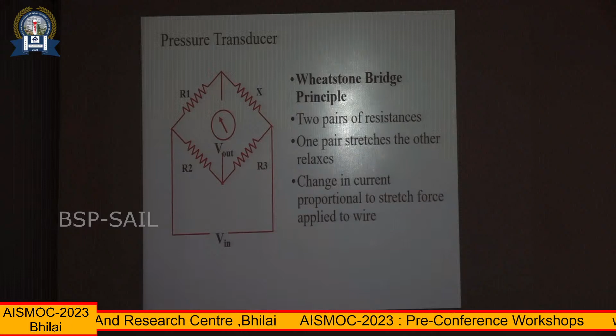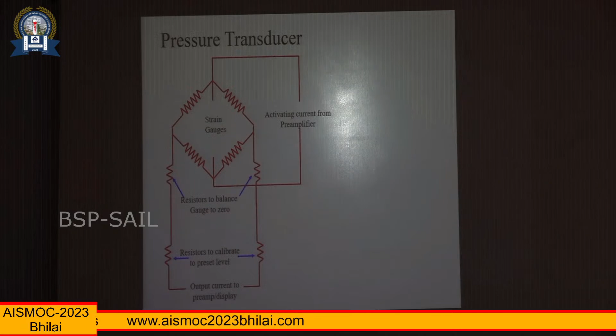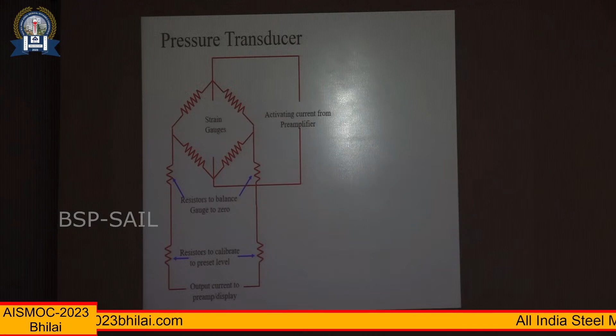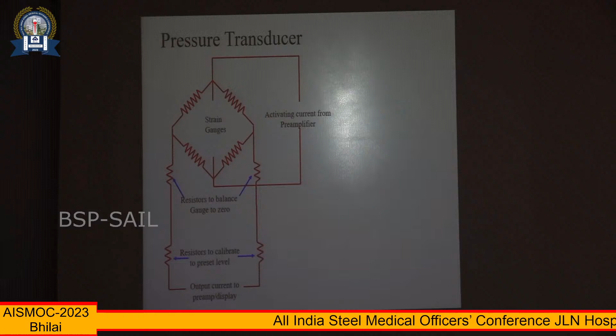transducer. Okay. To make the transducer more sensitive, the newer transducer, so previously we used to prepare transducers by ourselves, so we had reusable transducers, but nowadays we have the disposable ones. Previously we had to set up the diaphragm, make it less resonant, more low compliance, all these things we had to make. Now we get a commercially available transducer which is even better because it has 2 resistors applied in pair, so that it improves the signal to noise ratio. In other words, it makes it more precise.